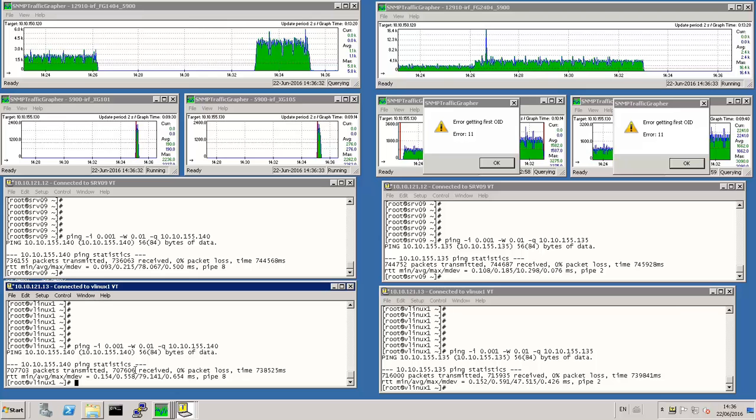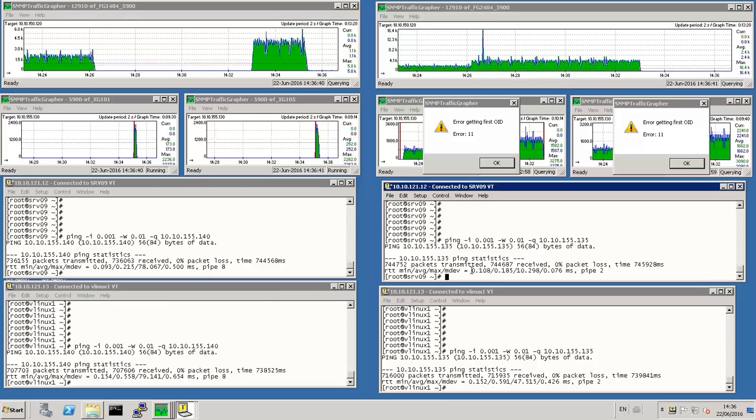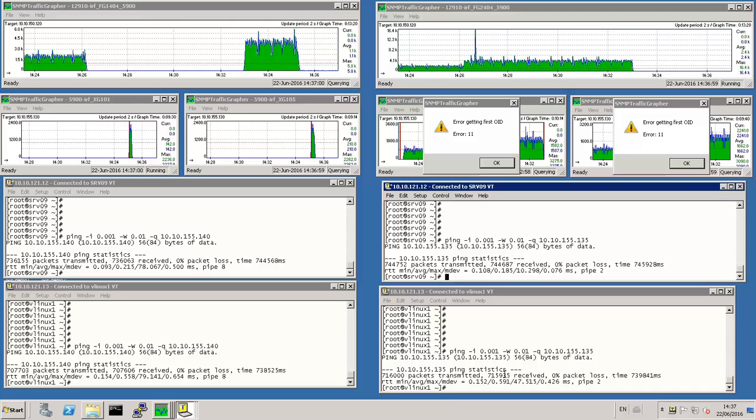Then on that one we have about the same, so 97 packets being dropped. On that one we've got 65 packets being dropped, and yes, that's it. And on that one, the last one, that is about the same, 65 packets being dropped. So a maximum of 227 packets being dropped.